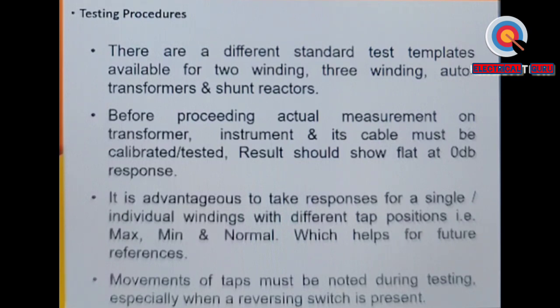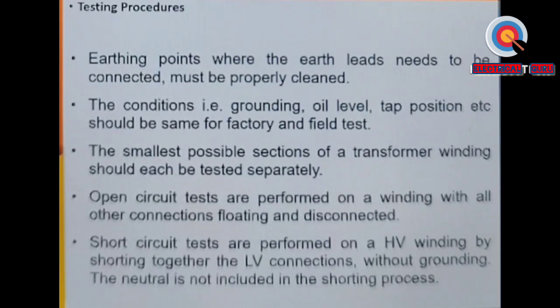Movement of taps must be noted during testing, especially when a reversing switch is present. So whenever we have to add or subtract, then we use the reversing switch, and that is how we change the direction of the current. Earthing points where the earth leads need to be connected must be properly cleaned. The conditions, that is grounding, oil level, tap position, etc. should be the same for factory and field test. The reason is that this is more of a comparative test, so we have to compare it in identical conditions.